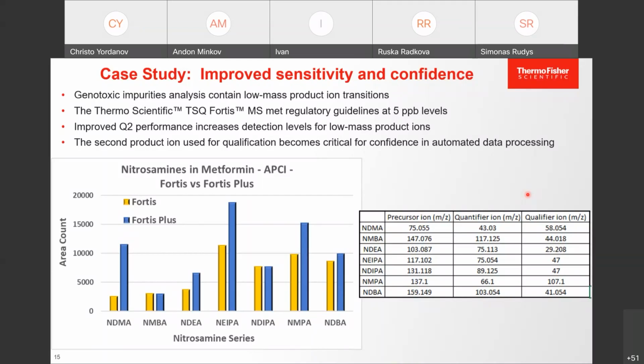When we look at the classical TSQ Fortis method, we already achieved the regulatory guideline of 5 ppb detection limit. But when we transfer the method from the Fortis to the Fortis Plus with the improved Q2 collision cell, we have much better low mass ion transmission. We can see the area count, the amount of ions transferred, and the blue line represents the Fortis Plus. So on every compound, every nitrosamine, we have an area improvement, so we can get even better results when you transfer the method from the Fortis to the Fortis Plus.